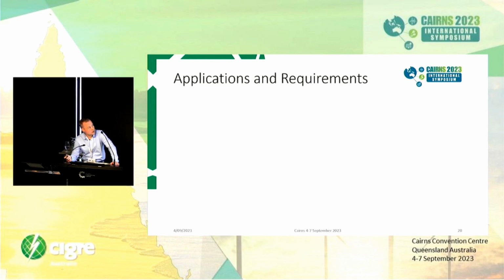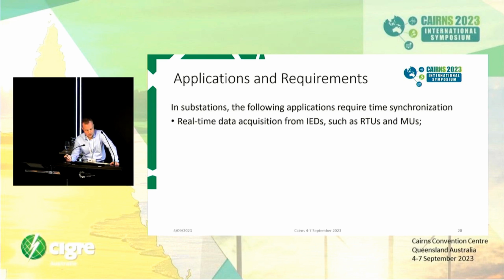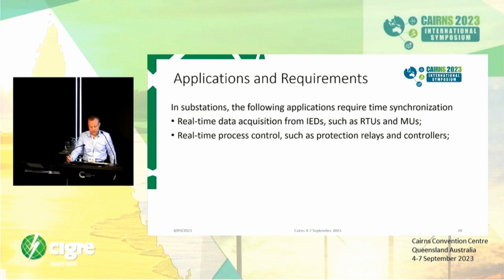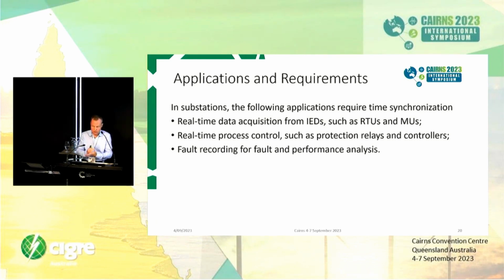Now we are jumping to that substation automation and protection camp. Who needs this automation? Everything that needs real-time data, real-time timing. So it means that you must always get the timing information for real-time process control, protection relays, that's important, controllers, fault recorders, synchrophasors. All these devices require accurate time, mainly time and date, to get the samples and measurement values at just the correct time.